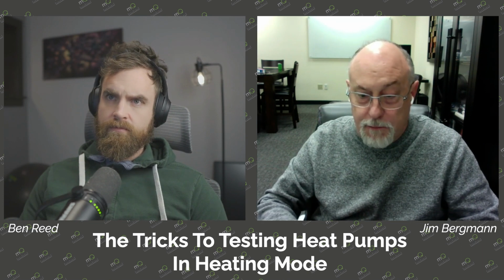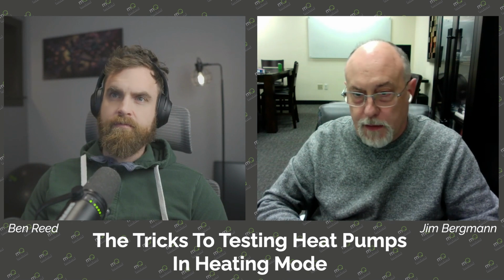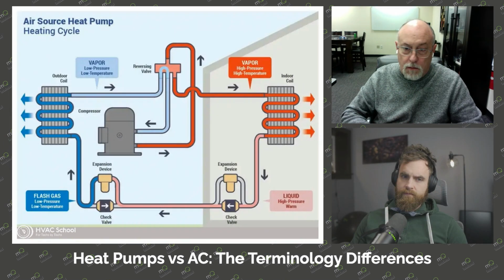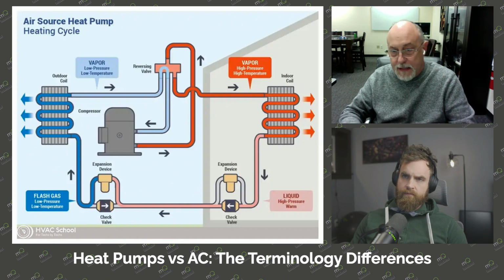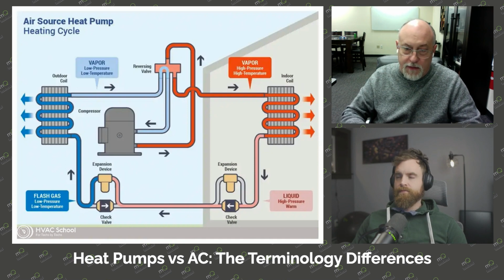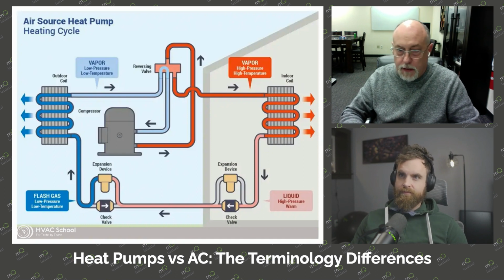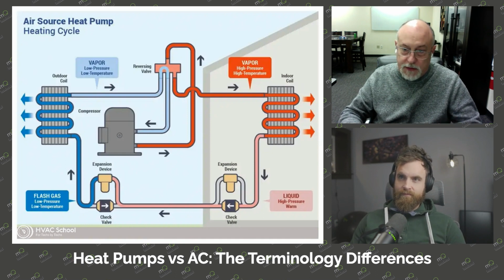Because on a heat pump we have an indoor coil and an outdoor coil, and the functions of those coils actually change. The outdoor coil can become the evaporator and the indoor coil the condenser in heating mode. In cooling mode, it goes just like we normally have, outdoor condenser and indoor evaporator. So now we've changed terms. On a heat pump, we have an indoor and outdoor coil. On an air conditioner, we have a dedicated condenser and a dedicated evaporator, a dedicated suction line and a dedicated liquid line. On a heat pump, those things change.